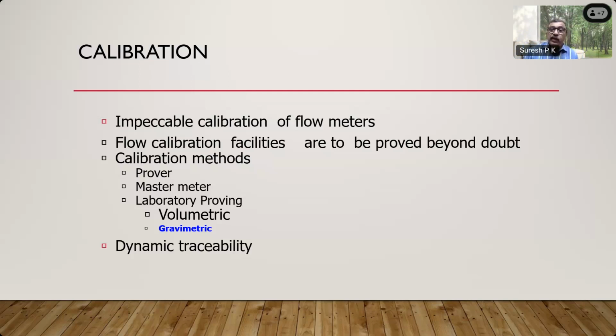So this has to be compared with the similar system elsewhere in the world. Say a flow meter which is calibrated at RRSL, for example, is taken to FCRA and calibrated at FCRA again, and whether you get the same kind of accuracy for both these systems is compared. That is called national dynamic traceability. And if you want international dynamic traceability, then a flow meter which is done at this system is taken to a system which is equally good, like say PTB Germany, or at FCRA we used to take it to NEL UK, or PTB Germany, or Delft Hydraulics, or Danish Technology Institute, or you can say Danish standards or Dutch standards.